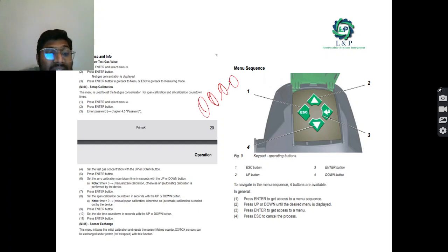Okay, and set the test gas concentration with the upward and downward arrows. Okay, and press the enter. Okay, set the zero calibration countdown time in seconds. The timing also you can change by pressing the upward and downward arrow, whatever required. Okay, by default it will be 0. If you want to make it up, you can press the upward arrow, 1 2 3, like that. You can change. If you want to make it down using the downward arrow, you can do it. Okay, once everything setting is done, please press the enter button, then only the value will be saved.